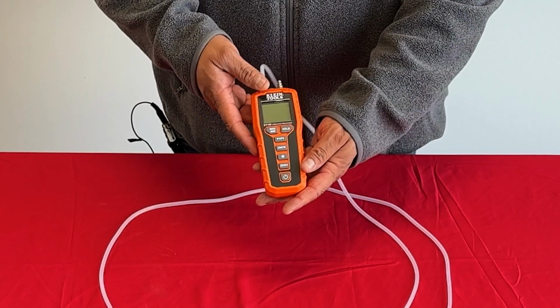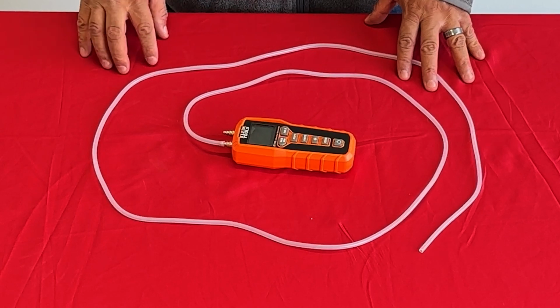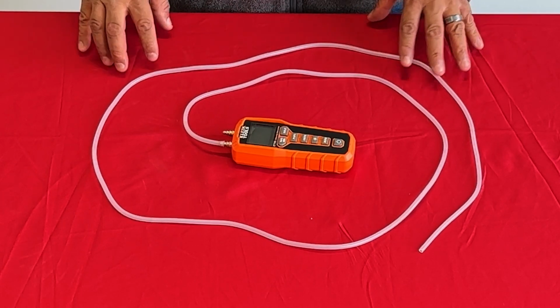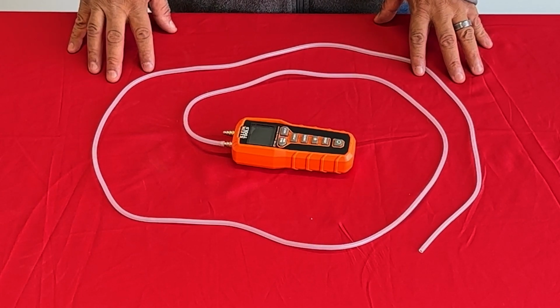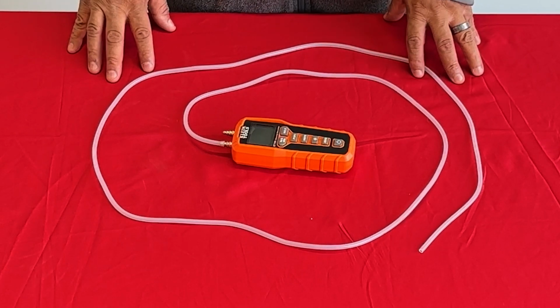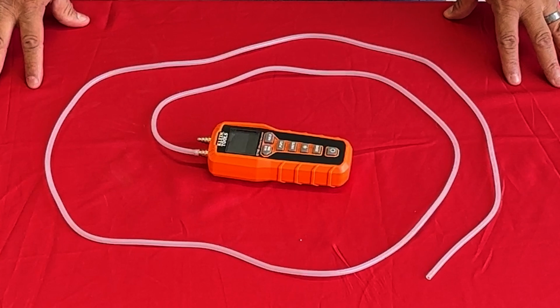The first tool we'll be looking at is a manometer. For hot side equipment, you're going to need a manometer to check your gas pressures. There's multiple ways to check gas pressure. You can check most of the time on a manifold. There should be a tap. Sometimes regulators have a tap, but you should almost always have a tap for you to check your pressure. The reason you want a manometer is to ensure that you have the correct gas pressure for the application you're working on. Each unit has a specific gas pressure that it should be set to.